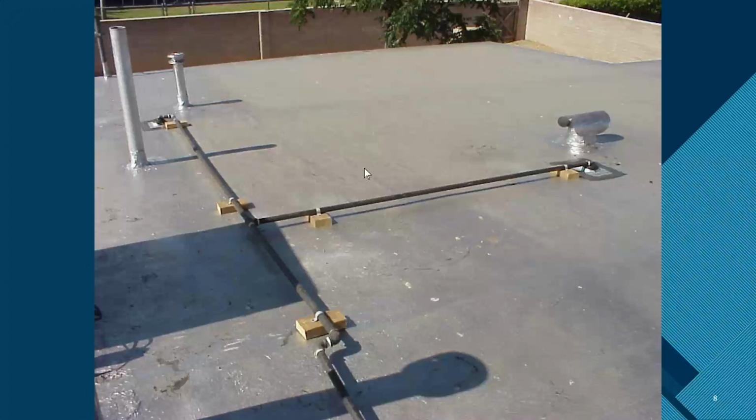So when you're looking at this and you see new plumbing, if it's a 1/2 inch pipe running to the stove and the water heater, it's most likely wrong. Again, someone will have to do a calculation. There's all these rules about being 10 foot long and a 1/2 inch and so on, but you're best to just write it up and have a plumber come and do the calculations.